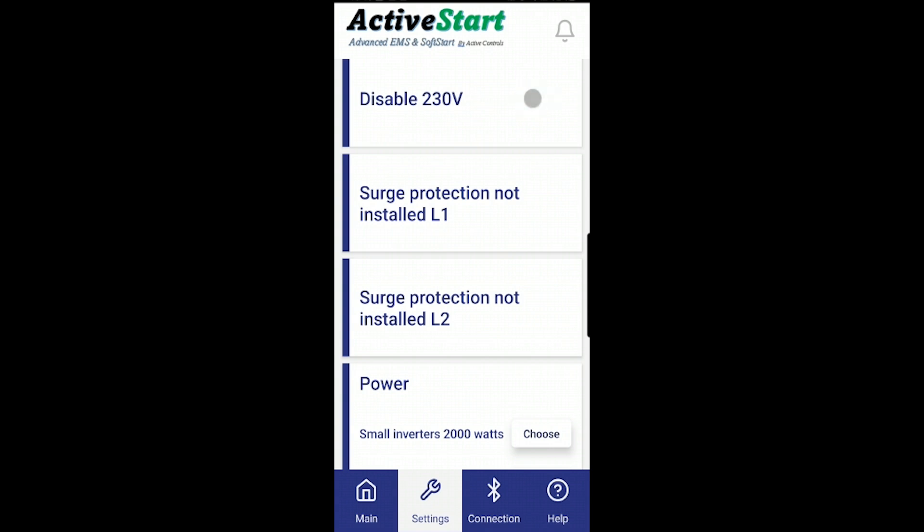It's very important to understand the 230 volt disable function — it only changes the shutdown condition. Both soft starters still work independently at all times. If there is a problem with incoming power we can shut down both outputs together, or shut them down independently.